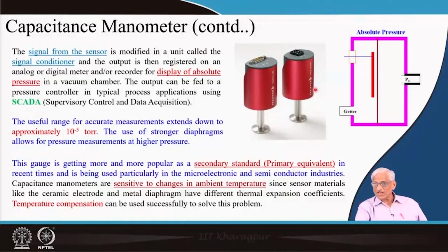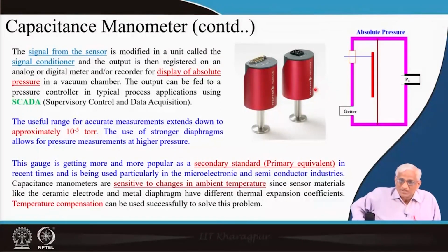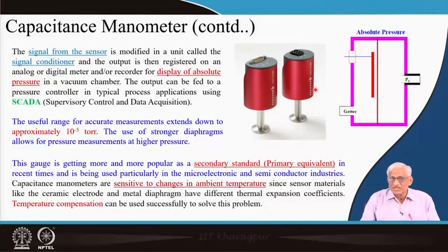In fact, in India we do not have a good manufacturer of gauges, because I know most of them. They are trying their best, but standard vacuum measurement requires very careful instrumentation knowledge, material science knowledge, and vacuum knowledge. So if anybody wants to have a startup on this manufacturing, with reliability and a little bit of standardization or calibration, it can be a very rugged and dependable gauge.